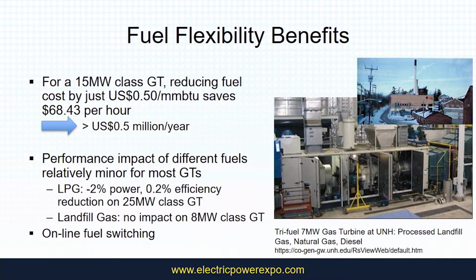Now, quick bit of maths. If I've got a 15 megawatt class gas turbine, then I can knock 50 cents per million BTU off my fuel bill. If I'm running for 8,000 hours a year, that's about $500,000 a year off my fuel bill, simply by fuel switching. And in reality on a gas turbine, switching between fuels has very, very little impact on its performance. And we looked at a 25 megawatt class on LPG, which is one of the worst cases. You lose 2% on power output compared to natural gas, and 0.2% on the efficiency.